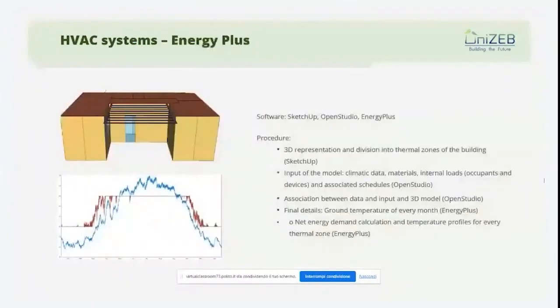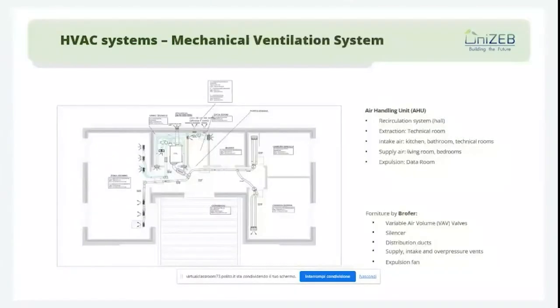We are also able to monitor this system. We have some anemometers inside the canals, the ducts. We measure the air velocity inside, the temperature and the relative humidity, so that we can check if the values we are setting in the system are actually the ones coming inside the rooms.